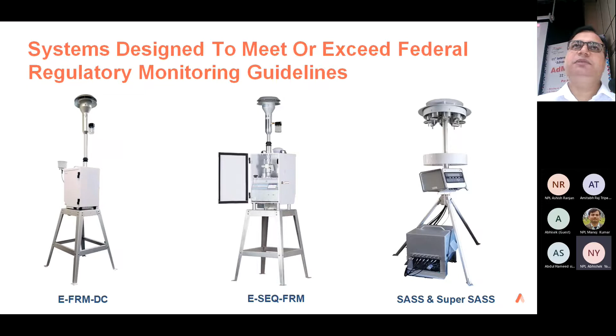The third one is a very special sampler, the SASS sampler or Super SASS sampler. That sampler is used for chemical speciation sampling. It has options for 5 inlets and 8 inlets, and with each inlet we can change the configuration. We can use PM2.5, PM1, PM10 and SPM; those 4 options are available. So simultaneously we can monitor different parameters. The dust is collected on the filter paper and then it can be used for chemical speciation.